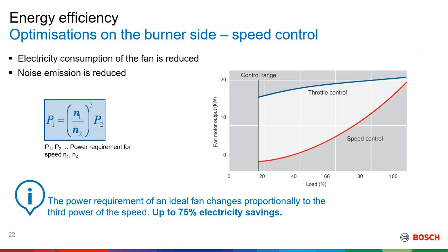Just by having speed controls on the blower fan, you're able to save around 75% of energy use, because there's a lot of wastage of energy of the blower and motor just by using dampers to choke the amount of air that is flowing into the boiler. So on the right, you'll see a curve of speed control and throttle control. And you can see the speed control will actually use less power when you're actually modulating the burner. Okay.